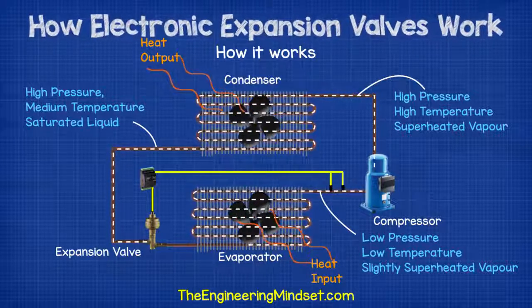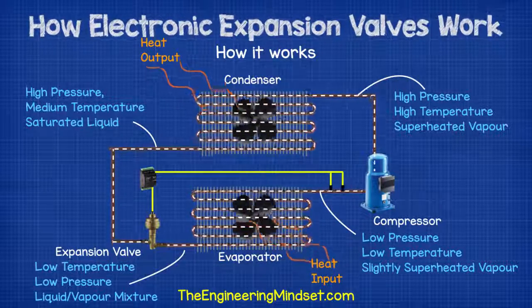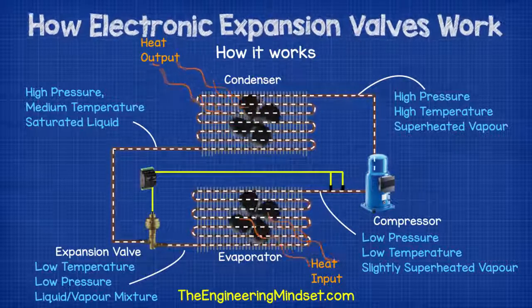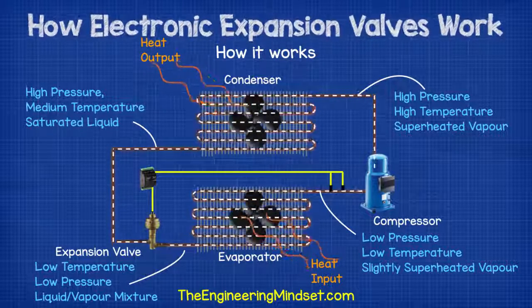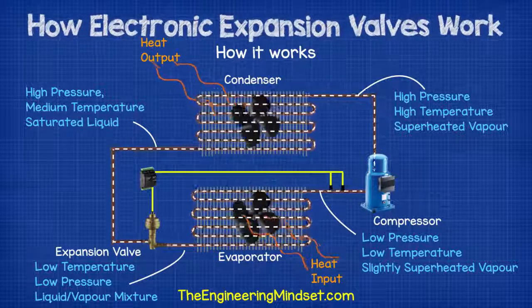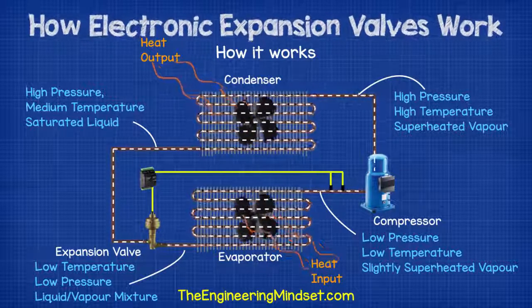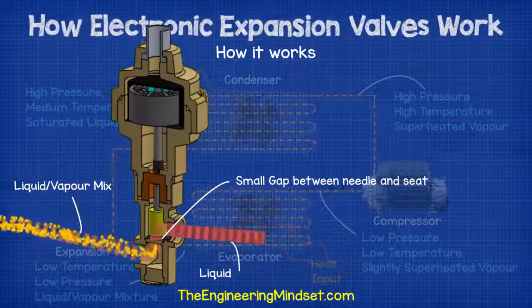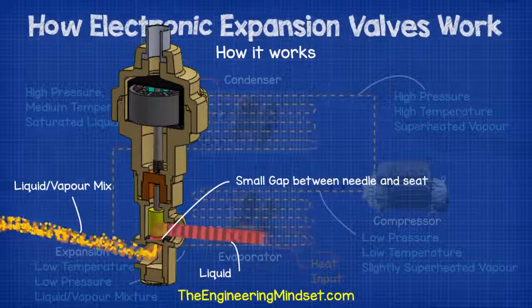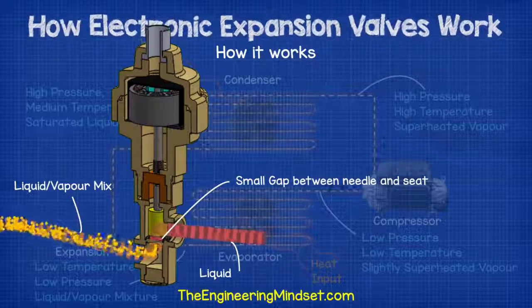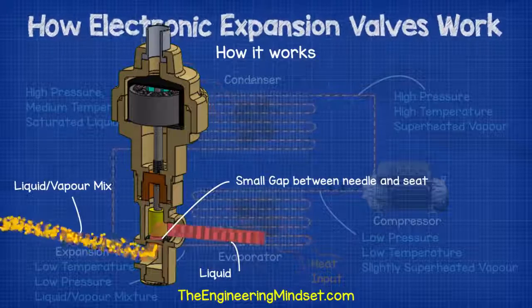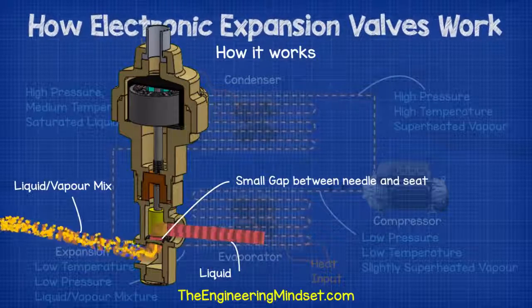It then passes down into the expansion valve. The expansion valve causes a pressure difference between the condenser and the evaporator. It holds back the high pressure liquid refrigerant and decides how much to let through into the evaporator. As the high pressure liquid refrigerant bursts through the small gap between the valve seat and the needle, it drops in pressure. This will result in some of the refrigerant vaporizing and the rest will continue through as a liquid.